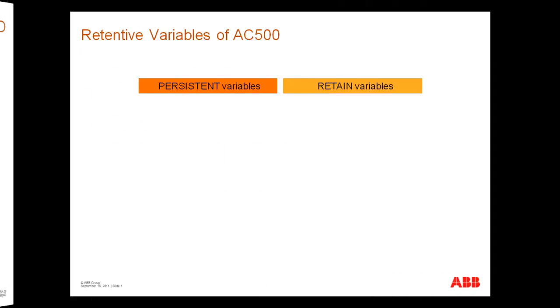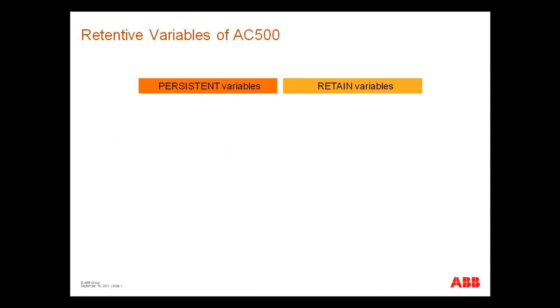We distinguished between two types of retentive variables of AC500: the persistent variables and the retained ones. Persistent variables maintain their value by project download. They are appended to the program code. Retained variables maintain their value after power supply off.